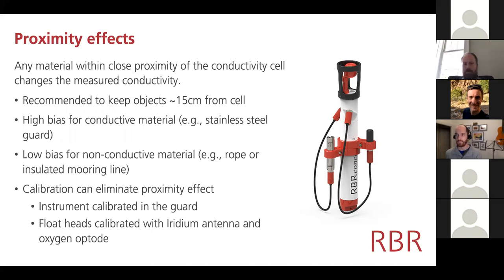So we have a rule of thumb, which is that we recommend that you keep objects 15 centimeters away from the cell. This isn't, of course, always practical. And so we have a number of ways of dealing with that. The first is that we can calibrate out the proximity effect of anything. So when we supply an instrument with a guard, it always comes with the guard calibrated in, and you don't need to think about that at all. When we supply Argo CTD heads, they always come with their antennas mounted and optodes or other connectors mounted, and we calibrate those out. But it's important to always have, and I think this is true across most engineering and science, a sense of proportion. How big is this effect? And is the effect big enough that it's worth worrying about?